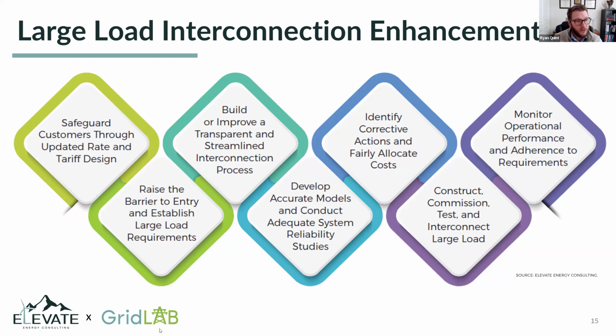Our warning signals shouldn't be 1,800 megawatt load loss events, they should be 20 megawatt load loss events. Say I saw one data center do something funky. I connected with them, and they told me they've got a protection setting set a certain way, and by the way, it's set that way for all their facilities. We could have a systemic risk here, and we should probably get on top of that. As opposed to: we just saw 60 data centers across a dozen substations and many different developers all do exactly the same thing, and we had no idea.